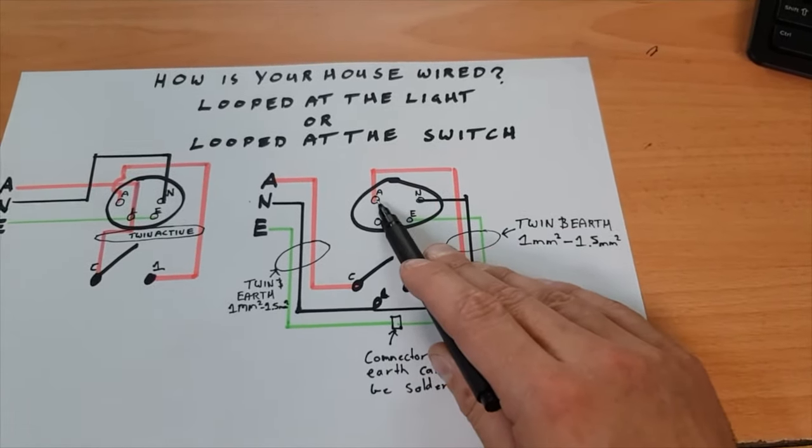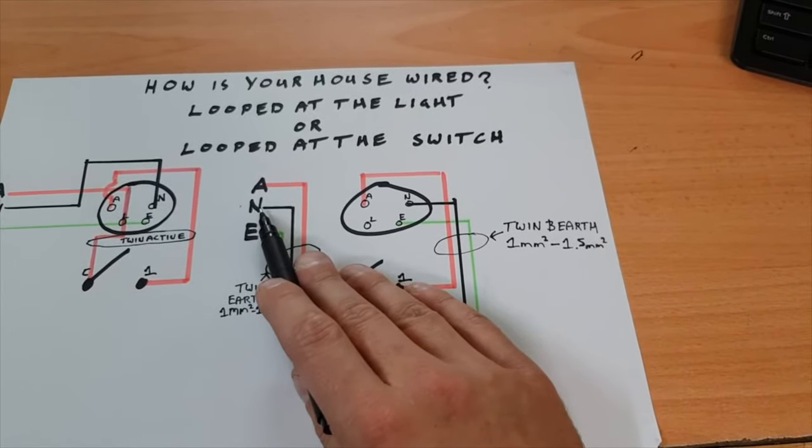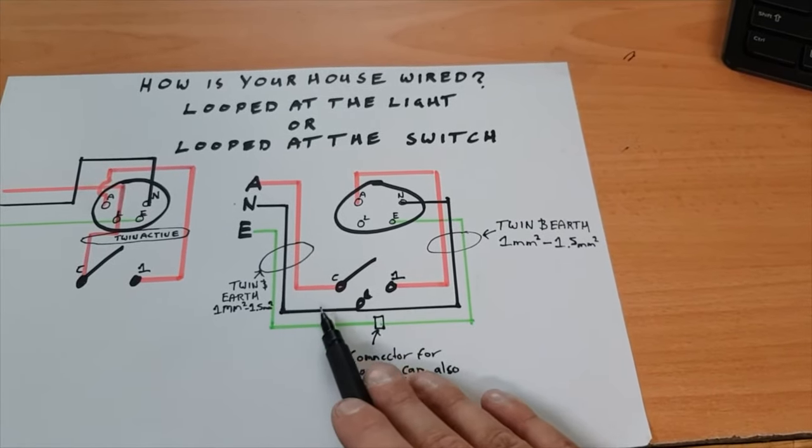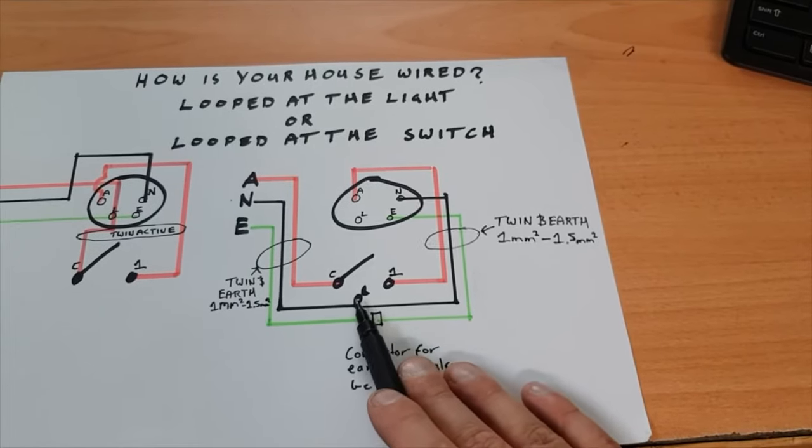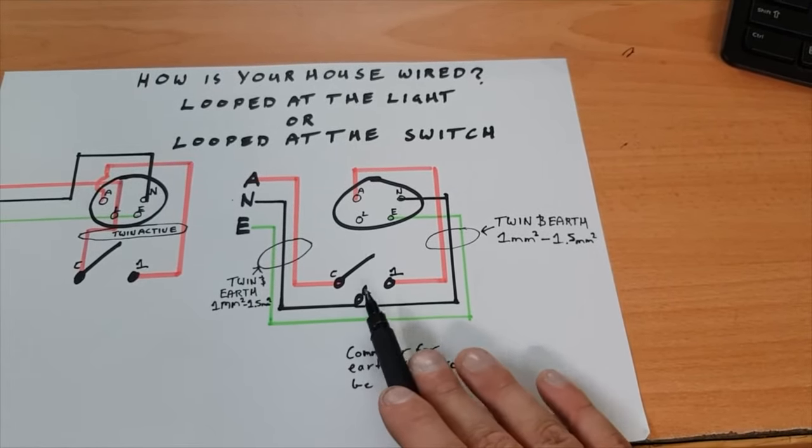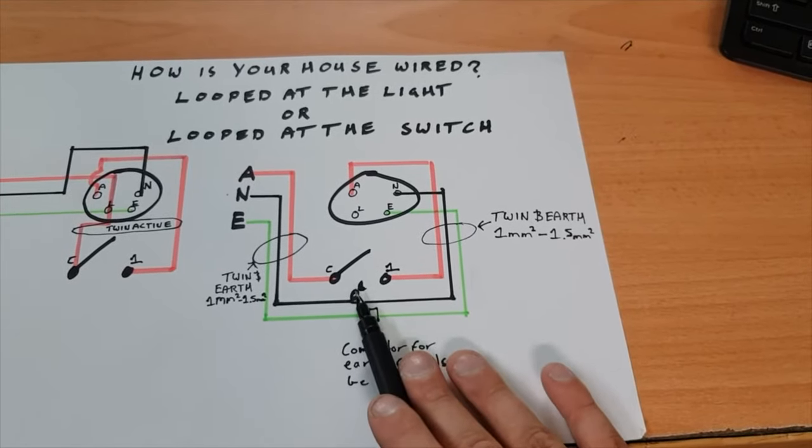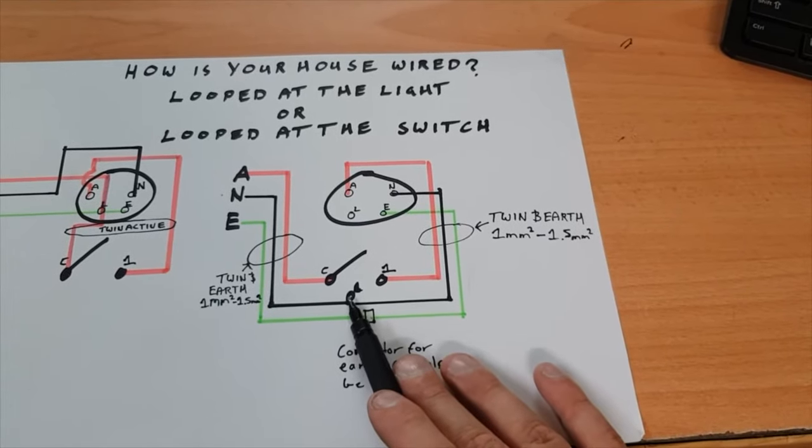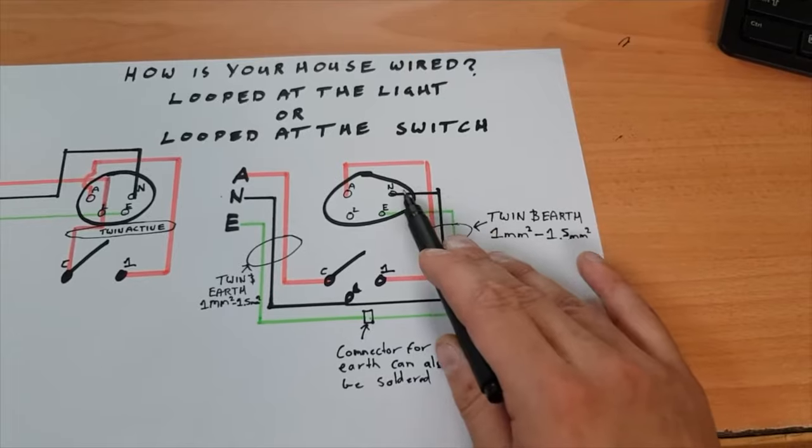And then your neutral goes straight from your neutral of your switchboard circuit breaker down here to your looping terminal, and it'll go into there, into your looping terminal or connector depending on how many other neutrals you have. It might be a bit squeezy to fit them all in this terminal, so you can use a connector. So from your looping terminal at your switch with your neutrals in it, goes up to your light neutral.